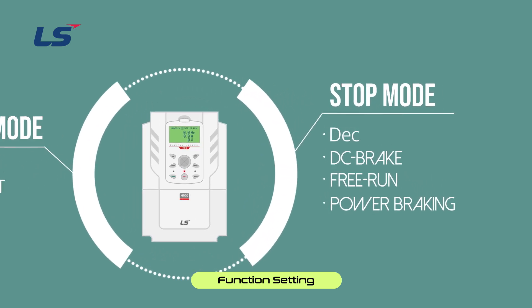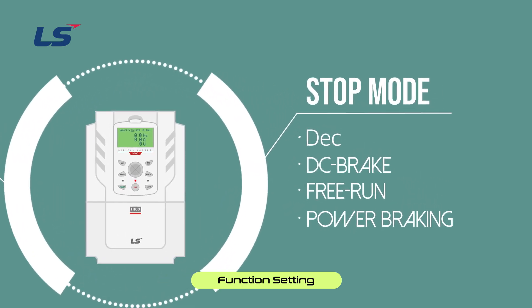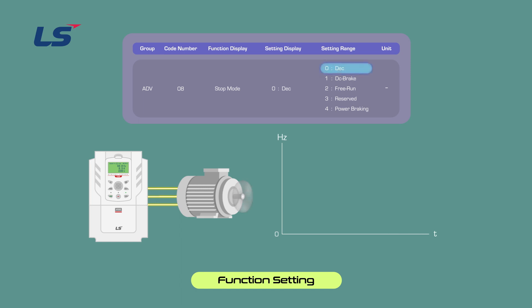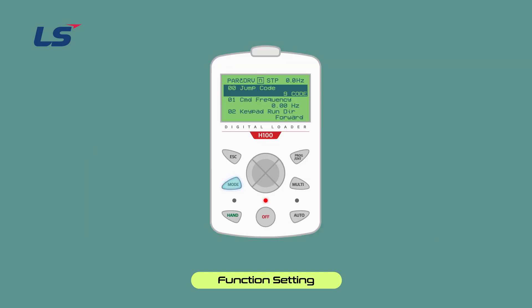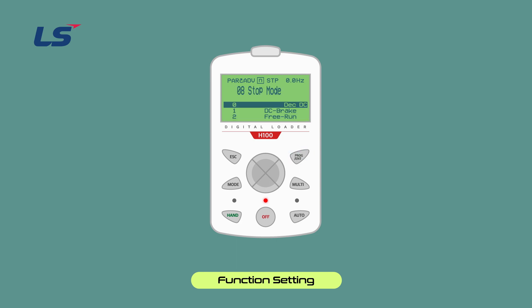Let's learn about stopping method settings. The DEC stop method is a general deceleration stop method. If there is no separate function selection, it decelerates to 0 Hz and then stops depending on the deceleration time. You can set the stop method by pressing the Enter key in ADV8 stop mode. Use the direction keys to move to 0 DEC and press the Enter key to complete the setting.